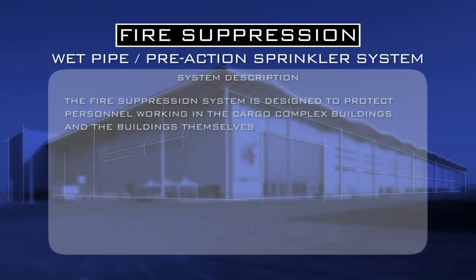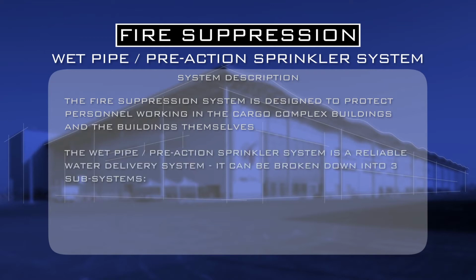The fire suppression system is designed to protect personnel working in the cargo complex buildings and the buildings themselves. The wet pipe pre-action sprinkler system is a reliable water delivery system and can be broken down into three subsystems: wet pipe sprinkler system, pre-action sprinkler system, and fire extinguishers.